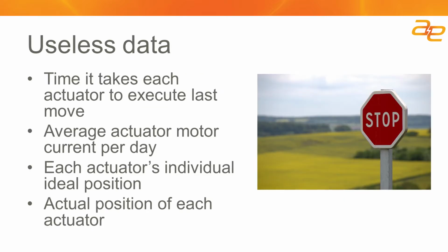Some of the things I see, like the time it takes for an actuator to execute a move, I don't see how that's valuable. If it takes longer than normal, I don't know what you'd do about that. It's actually more indicative to look at the highest actuator current to tell whether the system is working well. Average motor current per day is another value, but I don't know what the average really buys you.